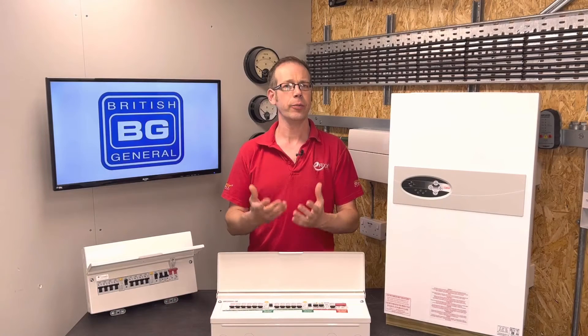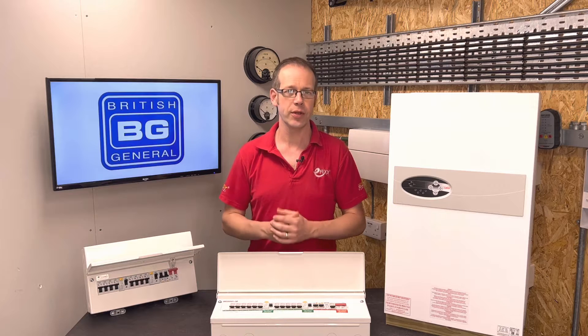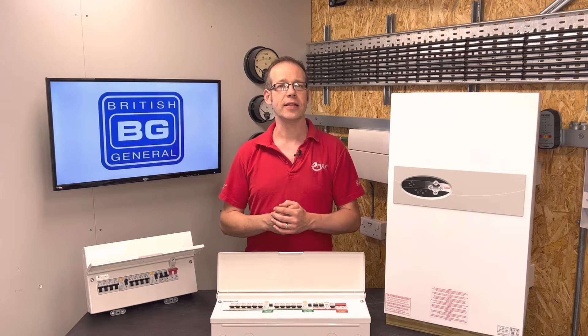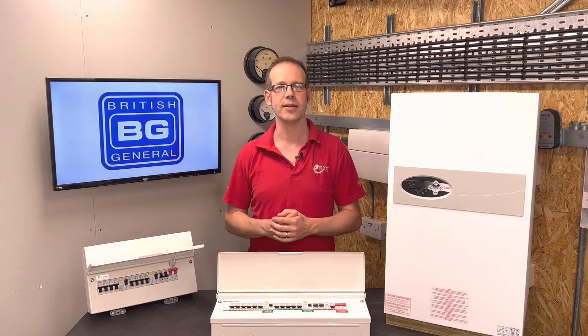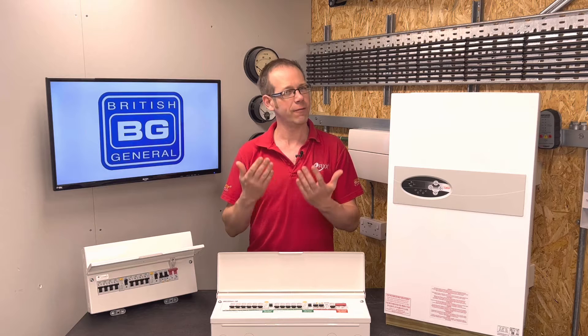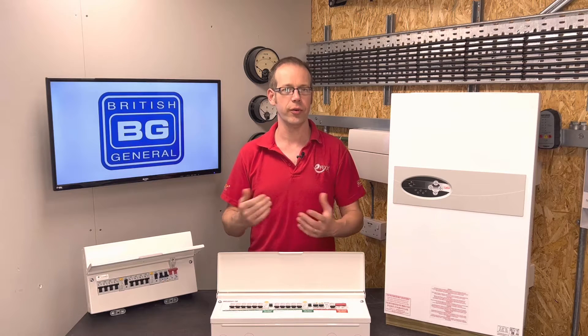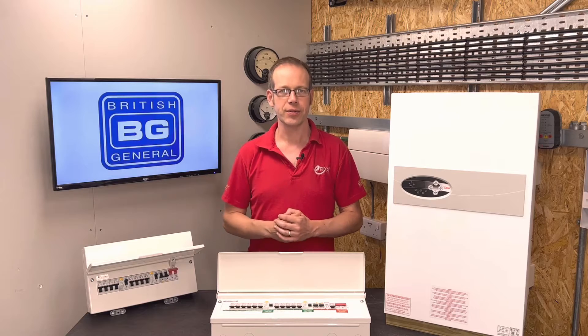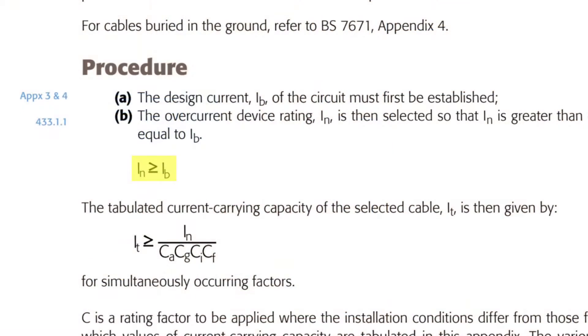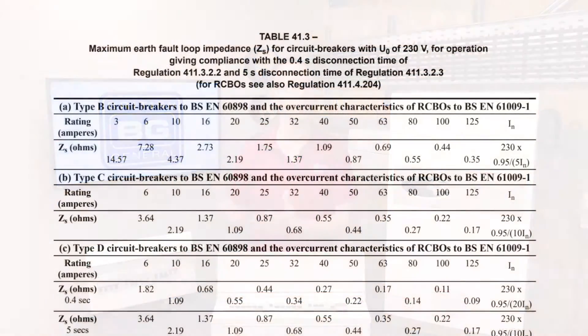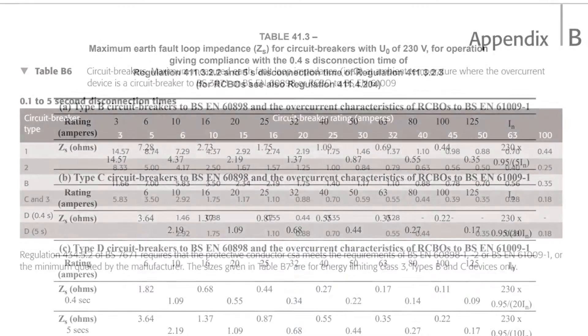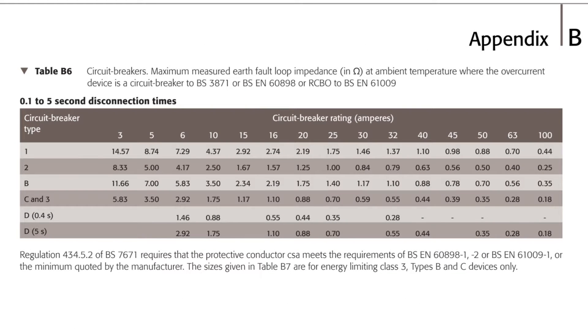We need to select an appropriately sized device from the range of protective devices. We're going to stick to MCBs for this task because, although it's still not unheard of to use fuses for final circuits, it's becoming increasingly unlikely they'll be used on new installations apart from certain niche applications. Since the nominal rating of the MCB needs to be equal to or bigger than the design current, we need to find the closest MCB above that value. We can consult a table of maximum earth fault loop impedances in either BS 7671 or the on-site guide to find the appropriate MCB size.